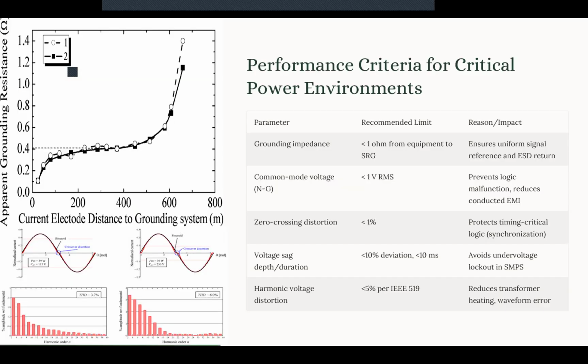Now, this standard also covers some performance criteria for the critical power environment. The first parameter is the grounding impedance. As we mentioned, our limit should be less than 1 ohm for a connection between the equipment and the SRG. We have a performance criterion for common mode voltage. Again, we mentioned it should be less than 1 volt RMS. We have a zero crossing distortion that should be less than 1%.